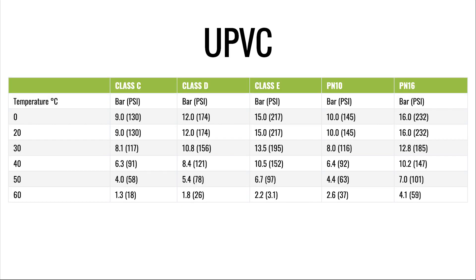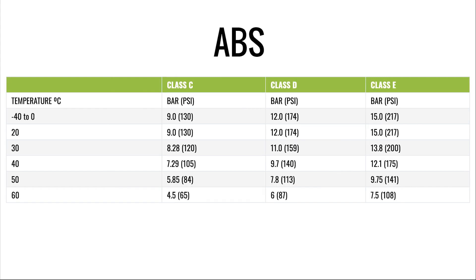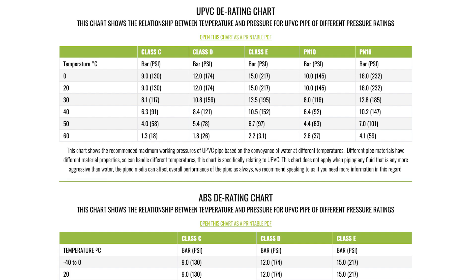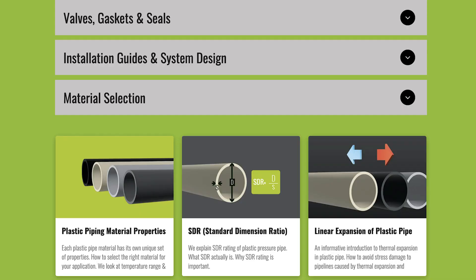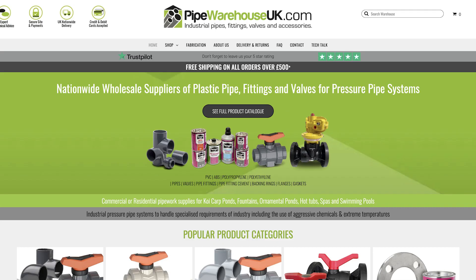Each plastic pipe material will derate differently, so consult a derating chart specifically for your plastic pipe material if you are expecting to pipe at elevated temperatures. Using these charts you can find the maximum operating pressure for different temperatures for UPVC and ABS pipe. Downloadable charts for all pressure pipe materials and other resources can be found over at pipewarehouseuk.com.